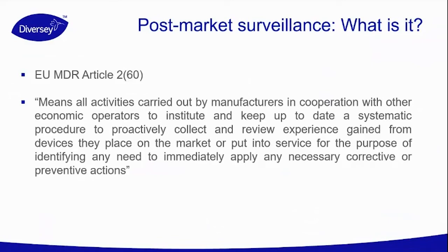Post-market surveillance means all activity carried out by a manufacturer in cooperation with other economic operators to institute and keep up to date a systematic procedure to proactively collect and review experience gained from devices they place on the market or put into service, for the purpose of identifying any need to immediately apply any necessary corrective or preventive action. In summary, post-market surveillance is important to collect in a proactive manner any feedback and experience gained from the market, from a customer, from sales, any feedback.